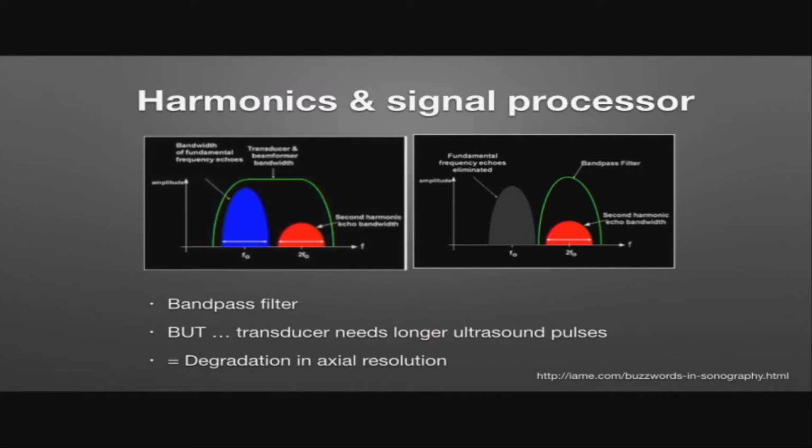Before we do, I just want to again concentrate on this band pass filtering initially. Look, because the fundamental and the second harmonic bandwidths must fit within the overall transducer bandwidth, it must mean that both of those fundamental and the second harmonic have got to have reasonably narrow bandwidths. Now try and remember that the bandwidth decreases with a longer pulse. Okay, so if I'm saying that I want the fundamental and the second harmonic frequency to have narrow bandwidth, I'm going to need a longer pulse.